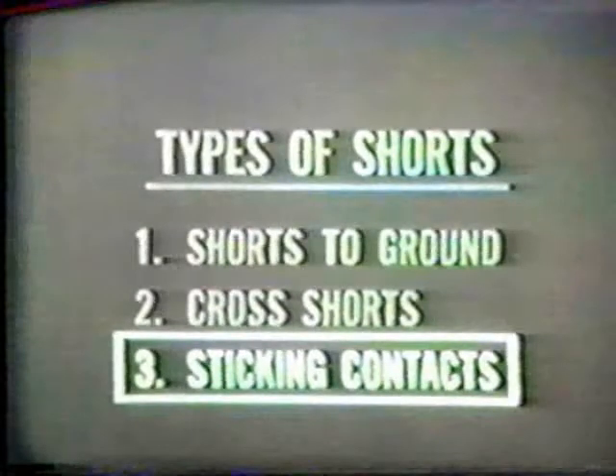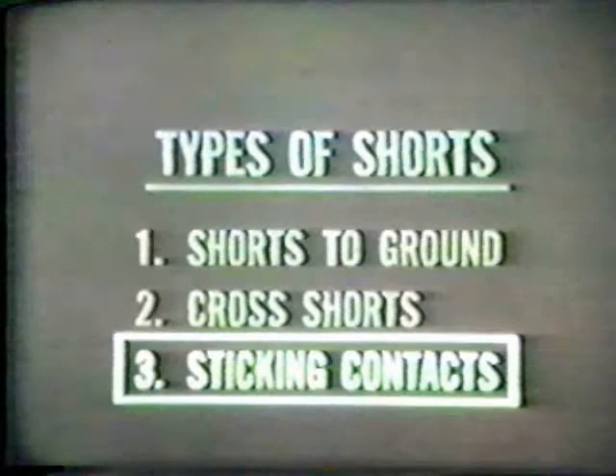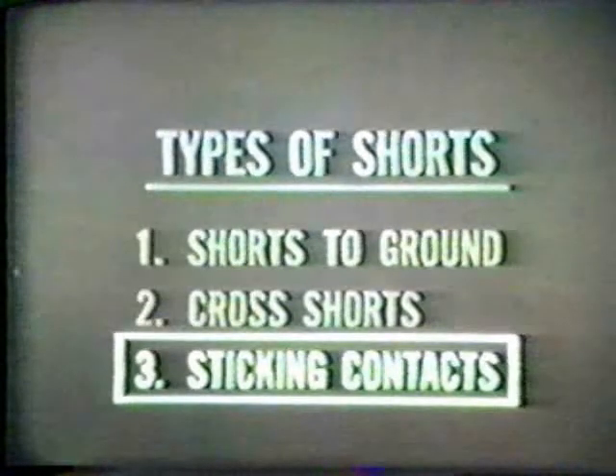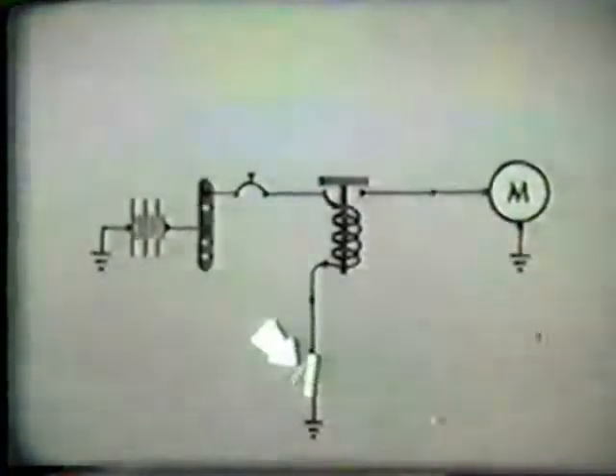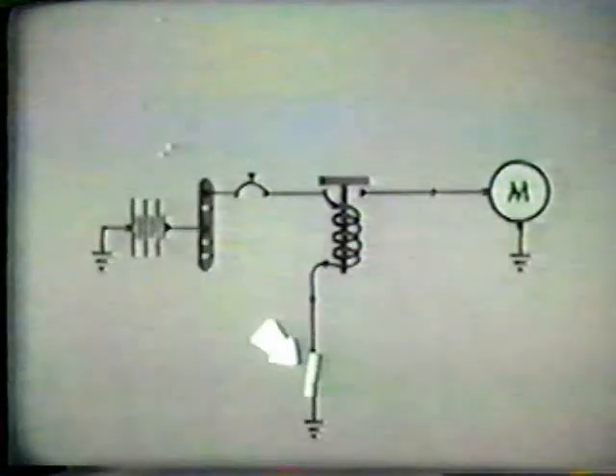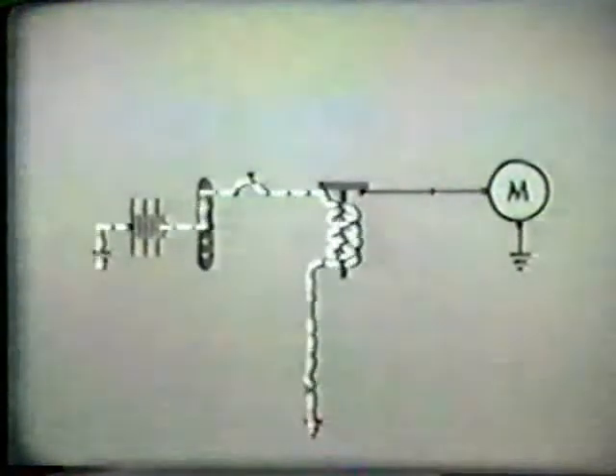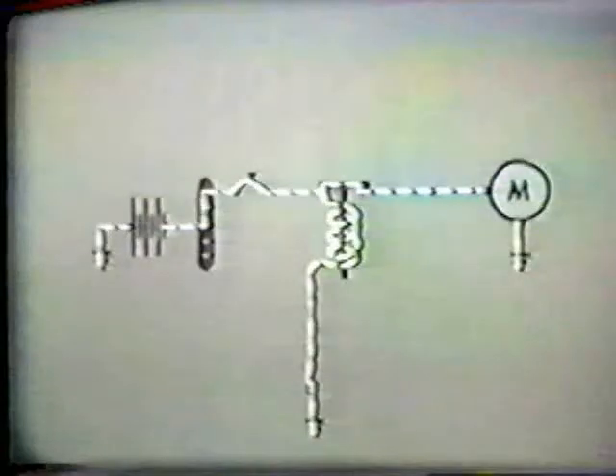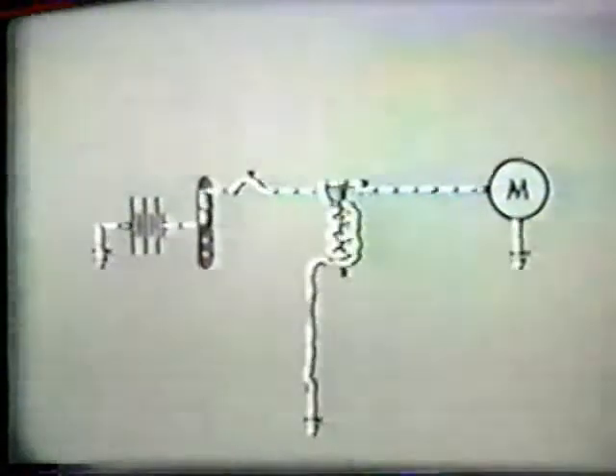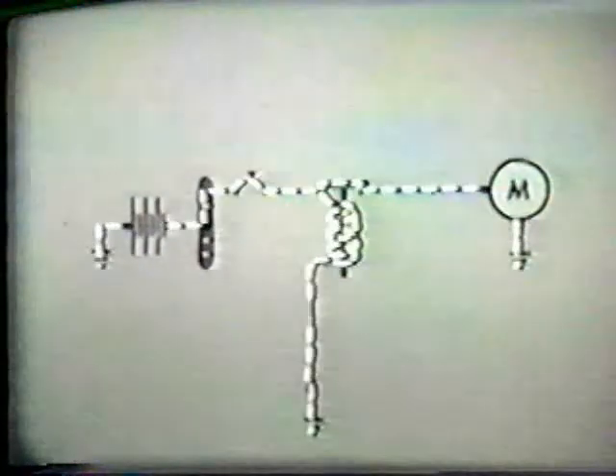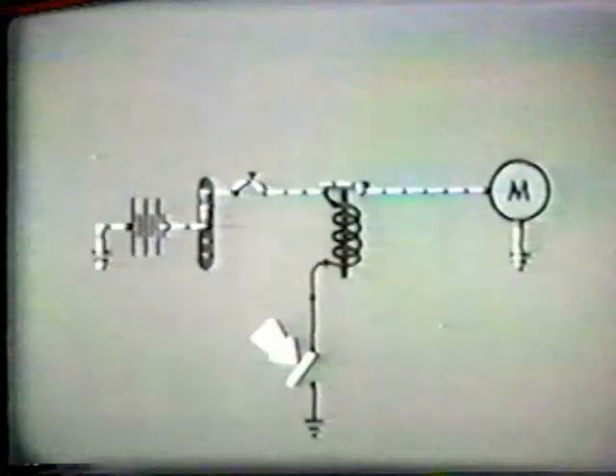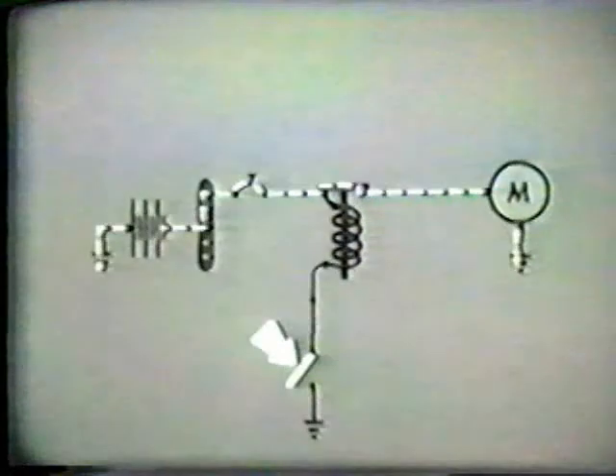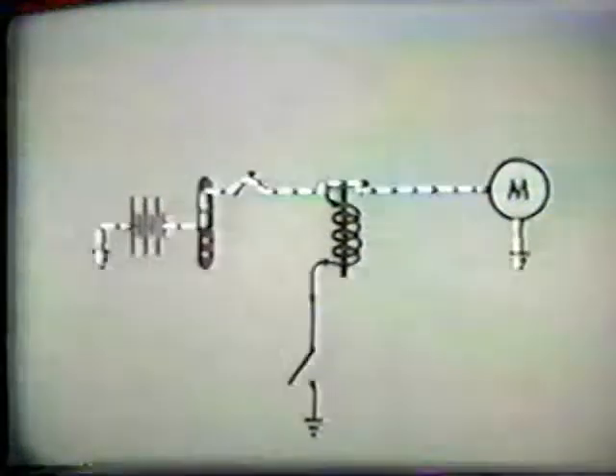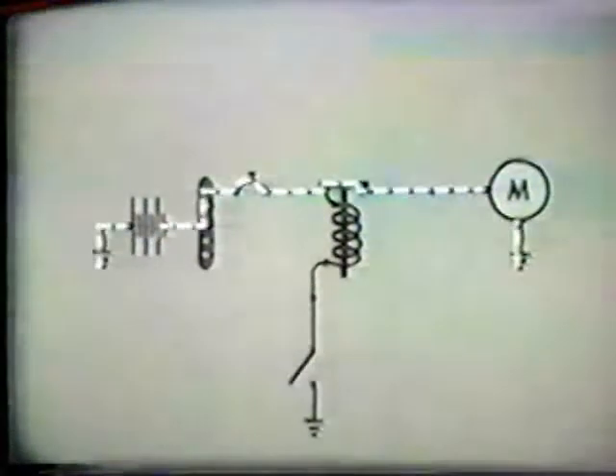Sticking contacts can also cause a short because they cause part of a circuit to be bypassed. A good example is a relay-controlled motor circuit. When the switch is closed, the relay closes and current flows to the motor. Normally, when the switch is opened, the relay will open and shut off the motor. When relay contacts stick, they stay closed even though the switch is opened. Current continues to flow to the motor or other unit. This is called a short because part of the normal circuit is bypassed. This could be caused by a defective relay or by a short in the control circuit.